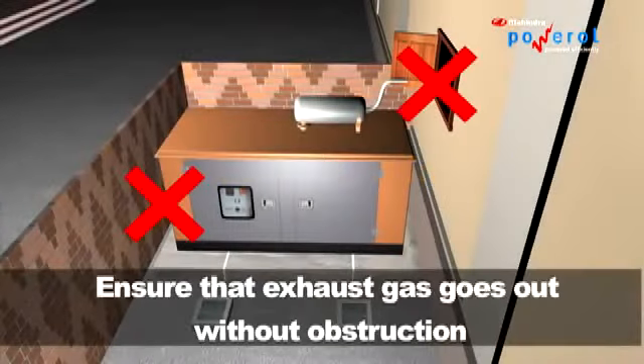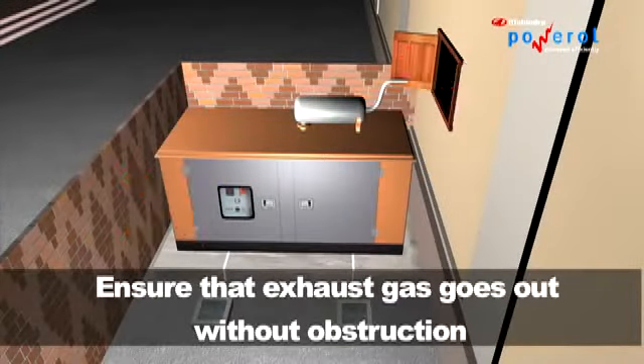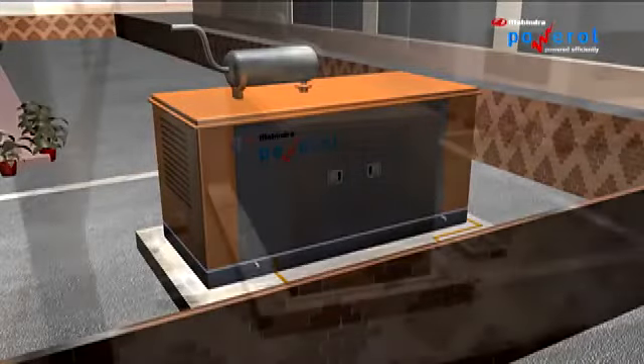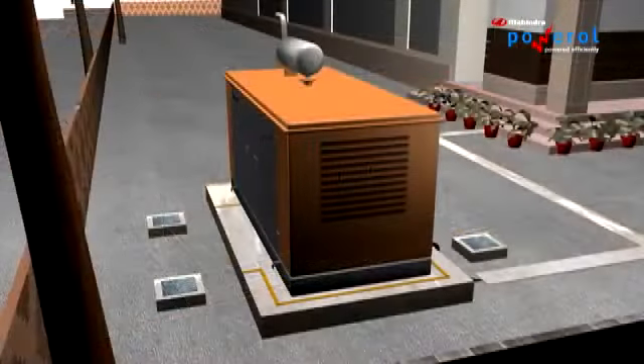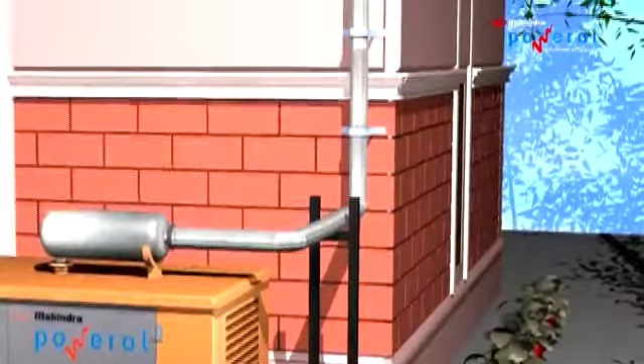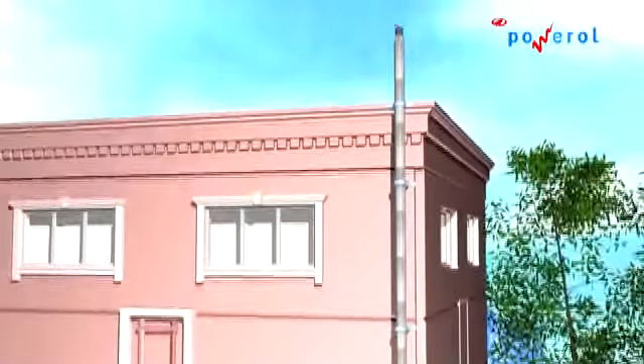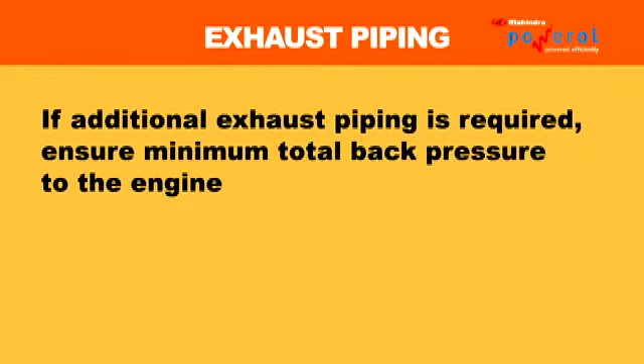Exhaust piping. Ensure that exhaust gas goes out to the atmosphere without obstruction. Exhaust piping run to rooftop should be through sound attenuated ducting. If additional exhaust piping is required, the exhaust pipe length should be as short as possible.